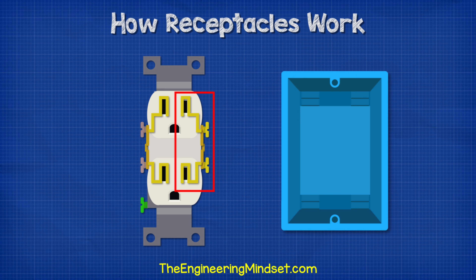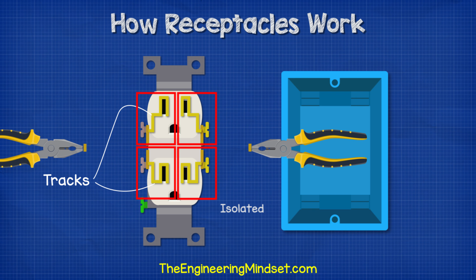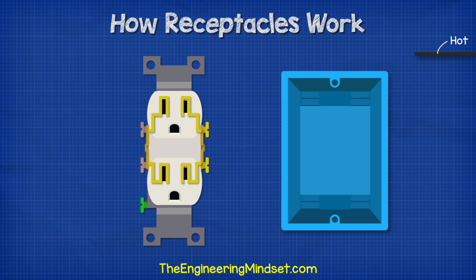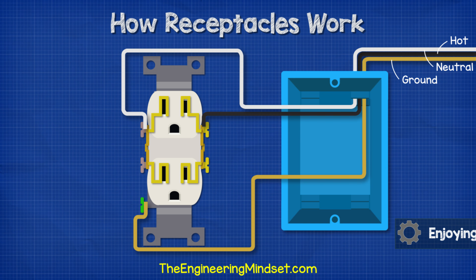We can remove the jumpers by using some pliers to just snap them off, but these can't be replaced. By snapping these off, we can isolate the terminals and connect them to different circuits. We'll look at this in detail a little later in this video. For now, I'm going to leave these jumpers in place. We can connect this receptacle into the electrical system by first bringing in our hot wire and connecting that to the hot terminal. Then we bring the neutral wire in and connect this to the neutral terminal on the opposite side. To make the circuit safe, we bring in our ground wire also.